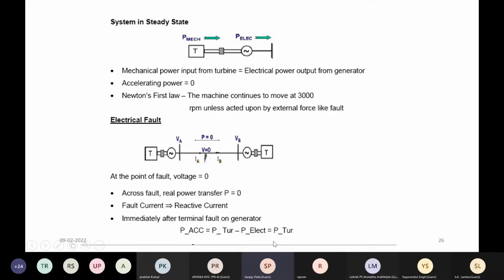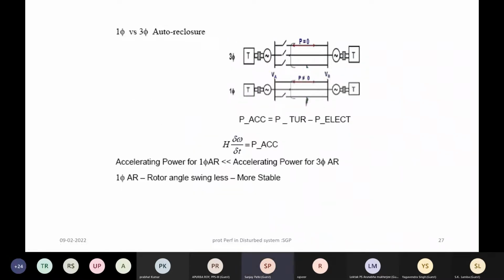And this is achieved through single pole tripping and single pole auto reclosing. By keeping two poles of the line intact, you allow active power flow on those two, and for the one phase which is open, the parallel line will correspondingly take the load, so that system stability will remain intact. So this is basically the accelerating power, and this accelerating power can be minimized. Instead of 3-pole opening, you are opening only 1 pole for a fault, thereby maintaining the integrity of the network as much as possible.